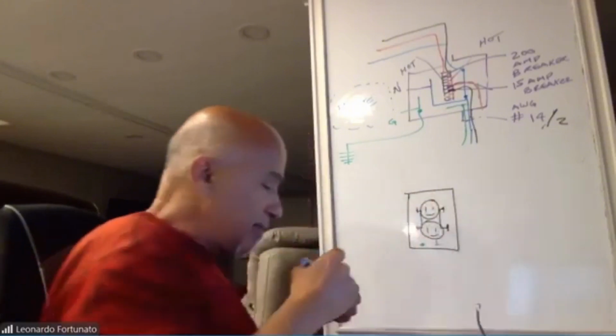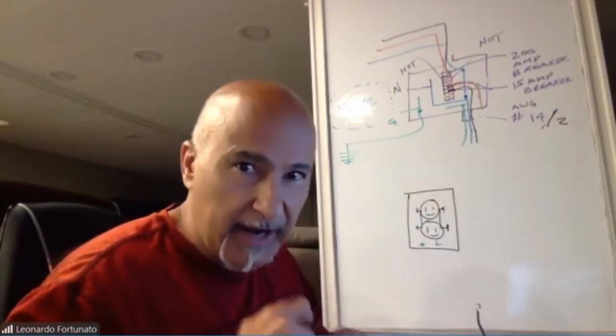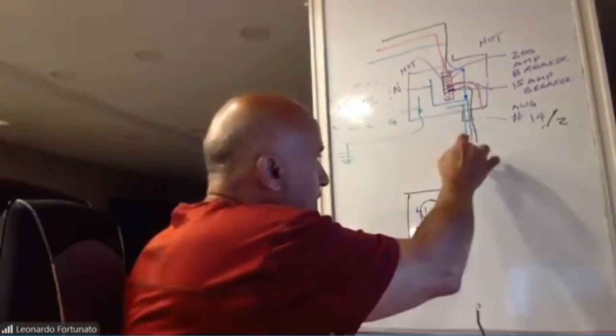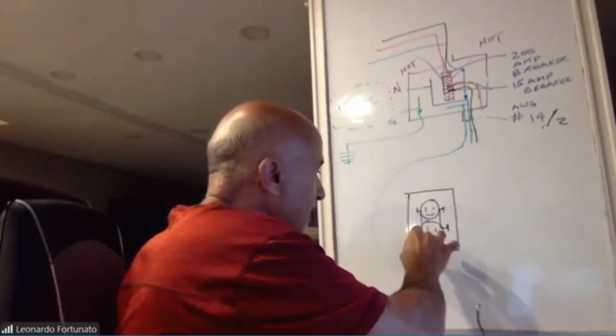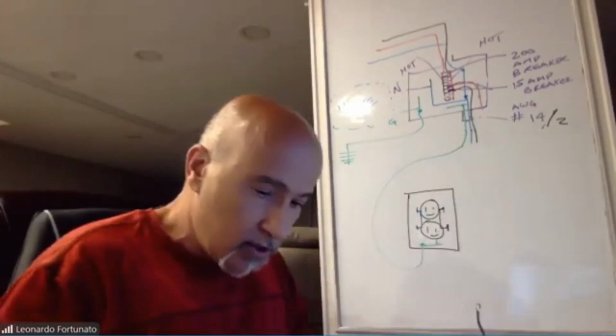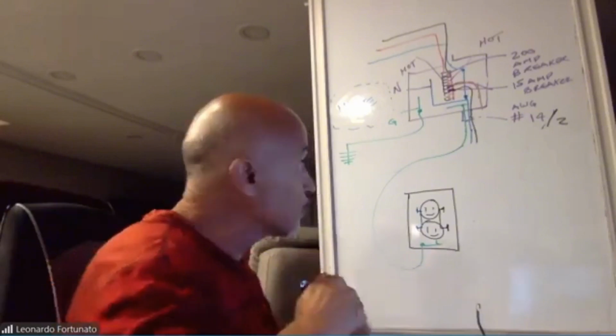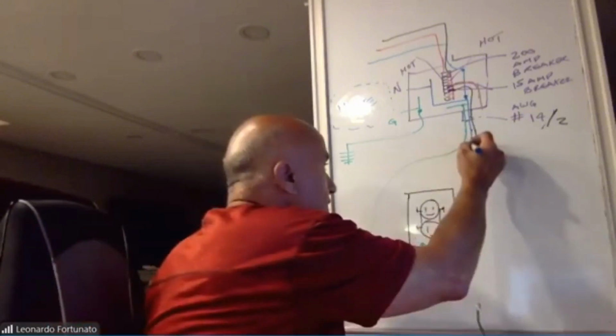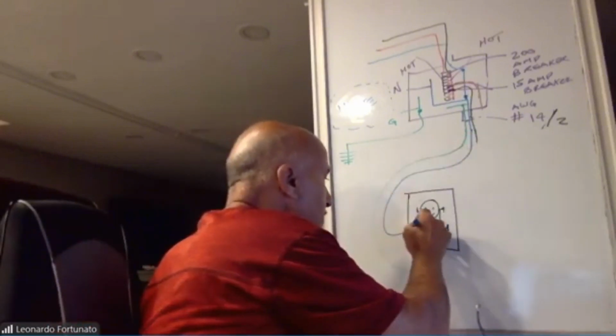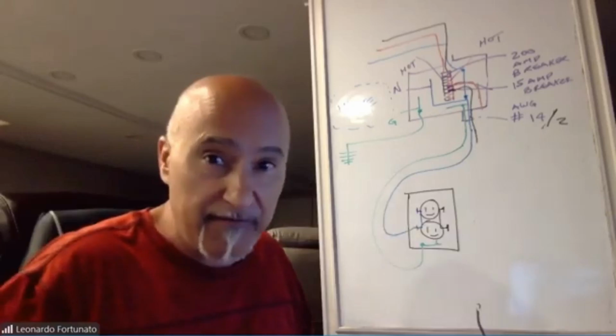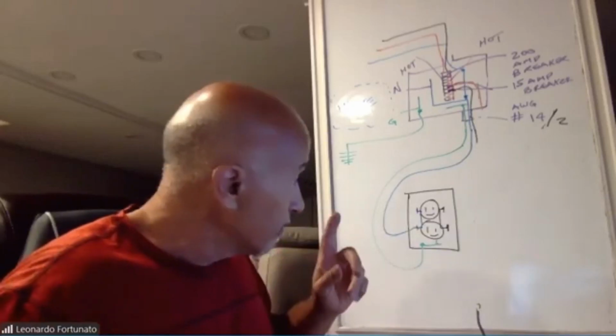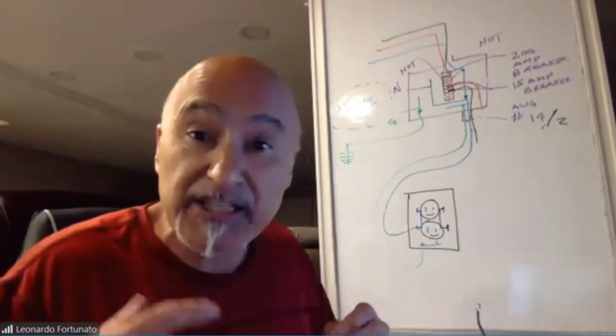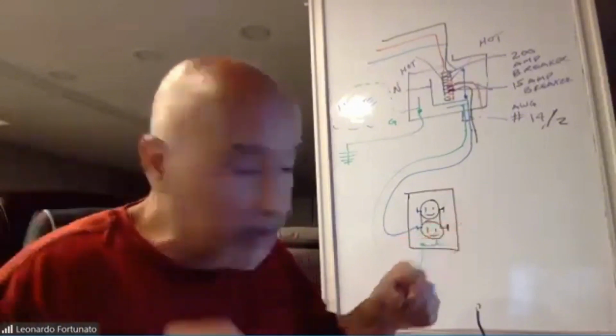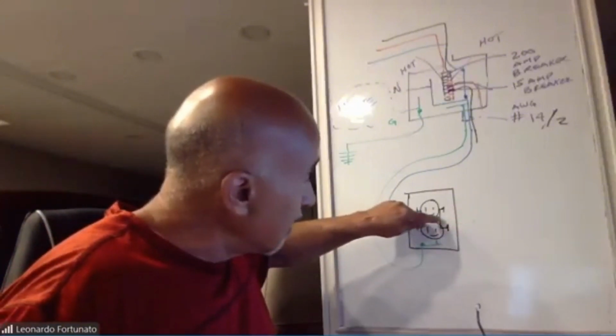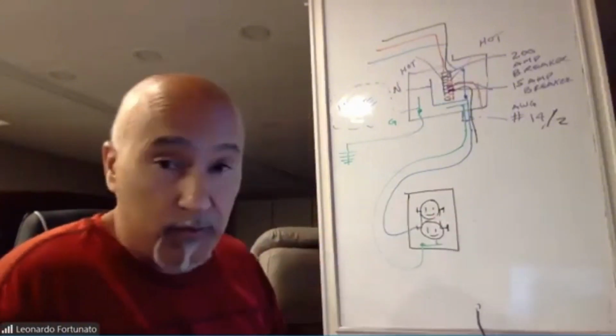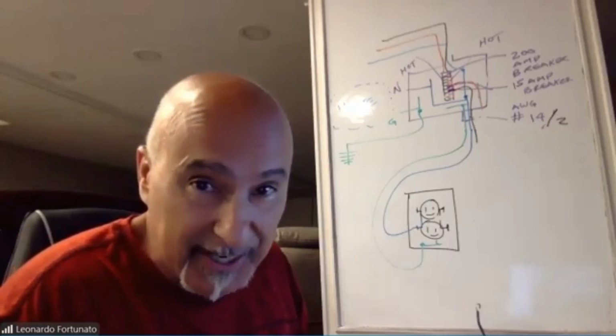We're going to start simply again with the ground connection. Ground bus bar, we come along, we've connected the ground. Do the neutral next - here's the neutral, come along, and we've connected the neutral. Fair enough? Now, in order for us to have a split switched receptacle, we again need to break that tab over there.